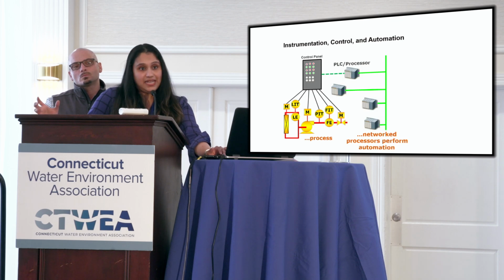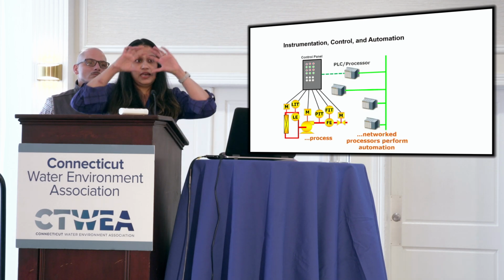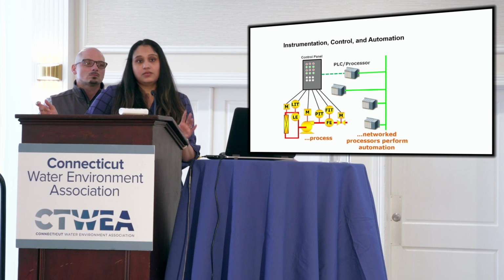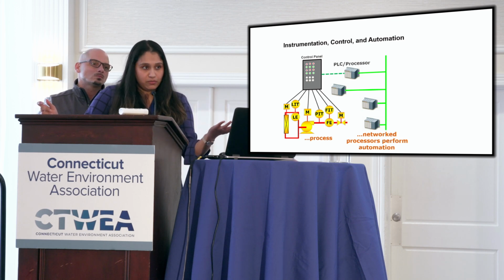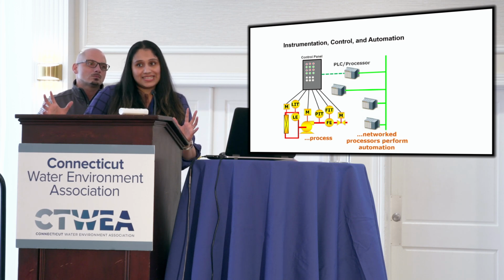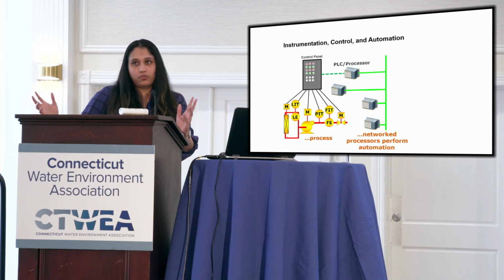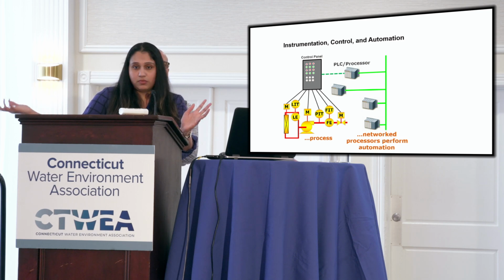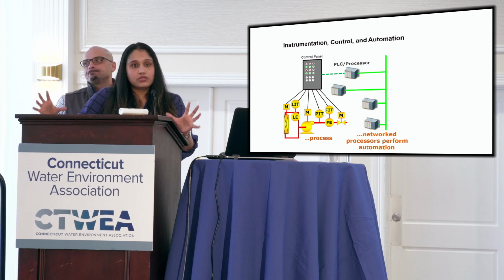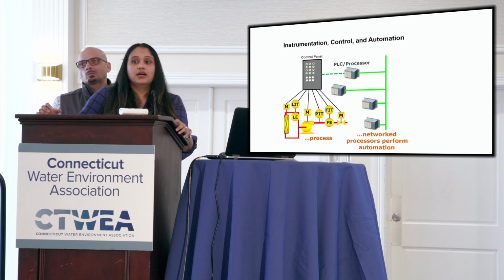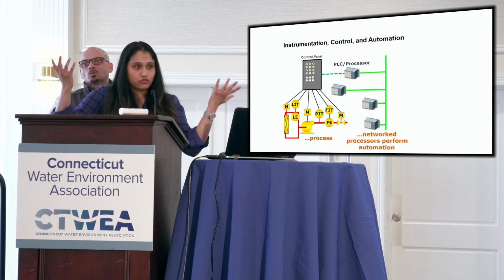But when we say Scada, it's not just the HMI you see on an everyday basis. HMI stands for Human Machine Interface. Scada is an overall system. Taking a bottom-to-top approach, you have all your field instruments—flow meters, pressure transmitters, gates, valves. All of those relay signals back and get tied into a control panel.